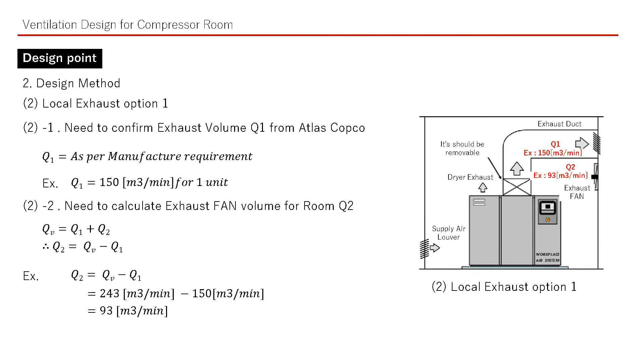We should decide two exhaust volumes. 1. Inside duct volume: confirm with the manufacturer. 2. Room exhaust volume: we can consider the remaining exhaust volume needed to remove heat generated by the dryer. Therefore, we can calculate Q2 as the room exhaust volume based on this formula. Please refer to the example.